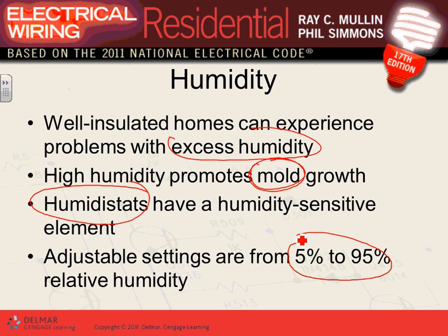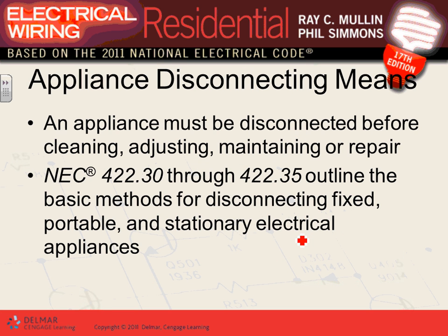What's in it for us, guys? I know this is dwelling. What's in it for us? If you have a humidistat and you need to set it, that's your controller for this particular fan. Something called the humidistat that you can power as your controller. These are your controller system, and adjust that. All these fans, guys, need a disconnect means. So exhaust fan, all of them need a disconnect means. A lot of these disconnect means for the exhaust fan can be as small as a 15 amp snap switch.